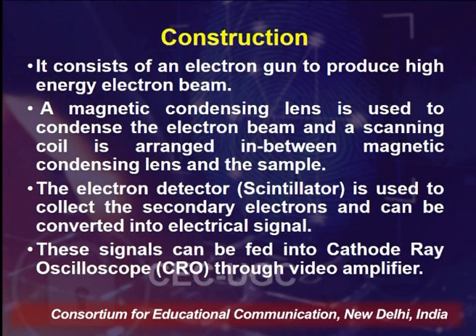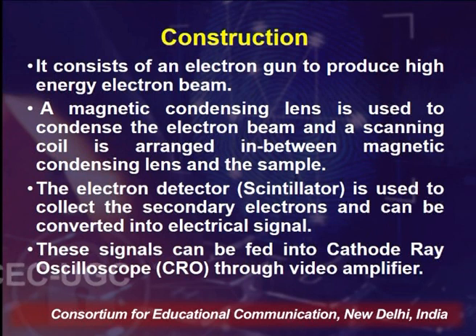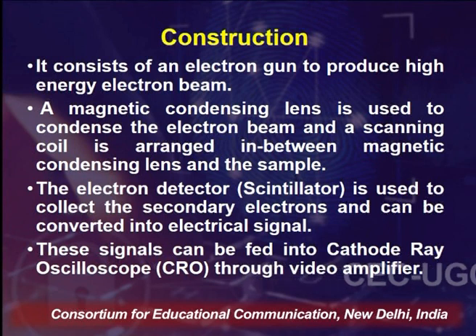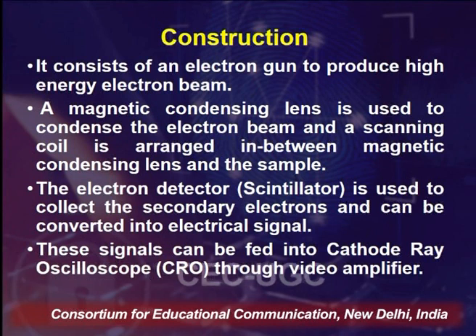TEM can be used for thin section samples; SEM for samples that are thicker in nature. SEM uses a finely focused beam of electrons to produce a high-resolution 3D image of the sample structure. It consists of an electron gun to produce a high-energy electron beam; a magnetic condensing lens to condense the beam; and a scanning coil arranged between the condensing lens and the sample. The electron detector (also known as a scintillator) collects secondary electrons and converts them into electronic signals, which are amplified by a video amplifier and fed to the CRO (cathode ray oscilloscope).